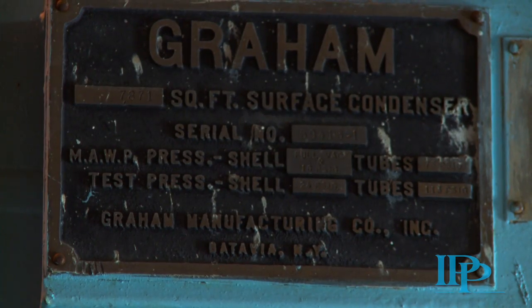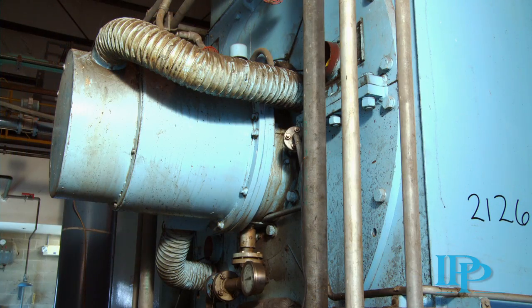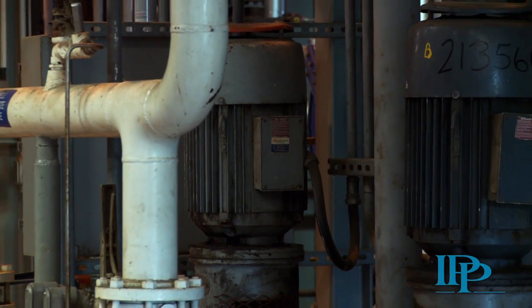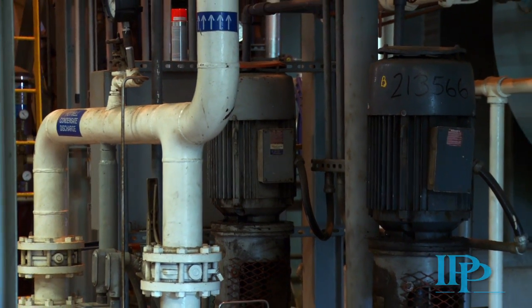The condensing is handled by a Graham 7,809 square foot shell and tube condensing heat exchanger. This condenser has a carbon steel shell and Admiralty brass tubes, and is rated for 86 million BTUs per hour.